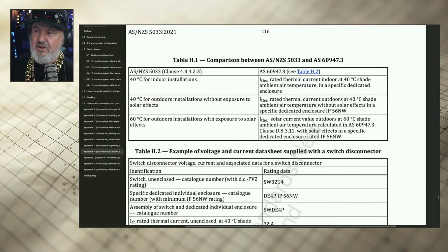So here's those temperature ratings for iThermal, ITHE. And you notice that there's 40 degrees for indoors, 40 degrees for outdoors without exposure to solar effects. So if you've got an inverter with a DC isolator on the wall, but it's not exposed to sunlight, then it's also a 40 degree rating required, a minimum 40 degree rating for your ITH. But if it is exposed to the sun, so whether it's on a roof or on a wall, then you need the 60 degree rating and that wonderful IP56 no water.